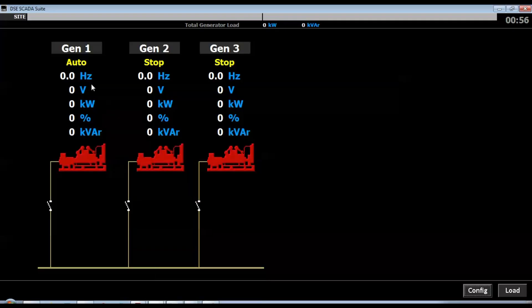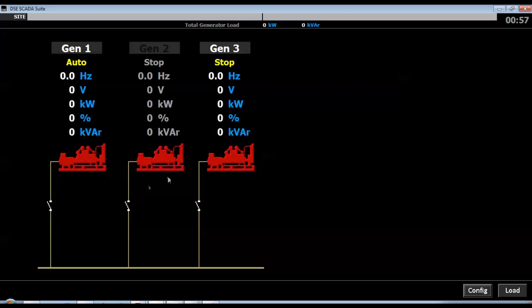Step 5: Disconnecting and Reconnecting. If an Ethernet cable is disconnected, the generator icon changes color to indicate it is offline. Reconnecting restores communication. The generator itself does not stop — it continues running. Only monitoring is interrupted.